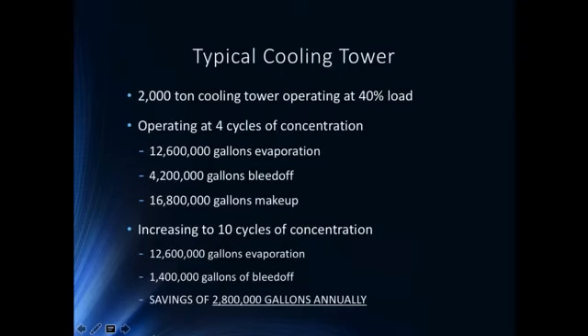And if you just use this simple example, 12.6 million gallons of water that's evaporated, if you can work with the city to get credit back for that by using water meters, then let's say an average is $3 per 1,000 gallons on the sewer side, that's $37,000 worth of money right there that you can get back by simply proving to the city that it's evaporating. And so, again, a tremendous amount of water we're talking about.